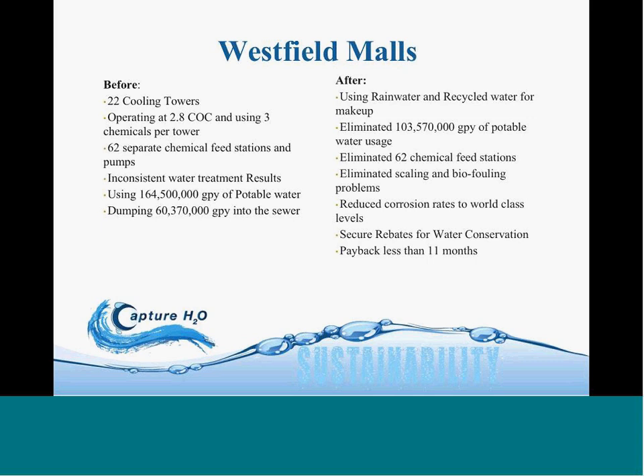After we installed our system, the Century City Mall is using rainwater and city water as makeup. Some of the other sites are using recycled water, air handler condensate. The Century City Mall is also going to have groundwater, so we're going to add that to that facility as well. But looking at the portfolio, we've eliminated a little over 100 million gallons of potable water usage, eliminated 62 chemical feed stations, and provided very consistent water treatment results, meaning no scale, no biofilm.